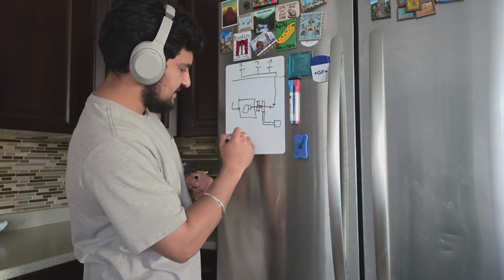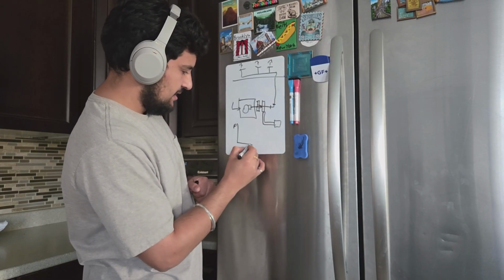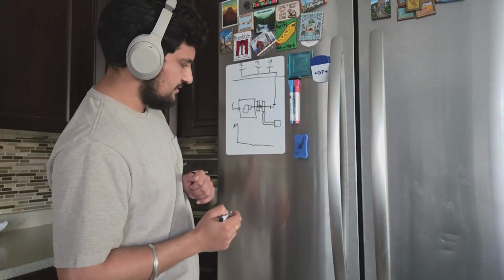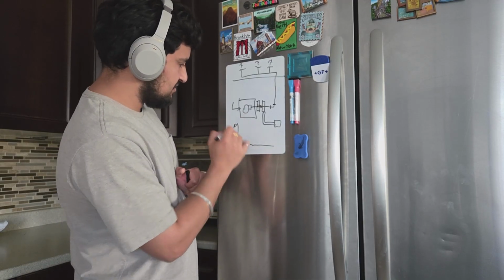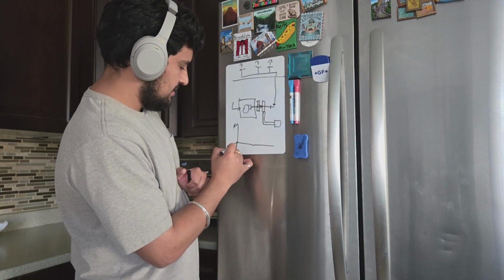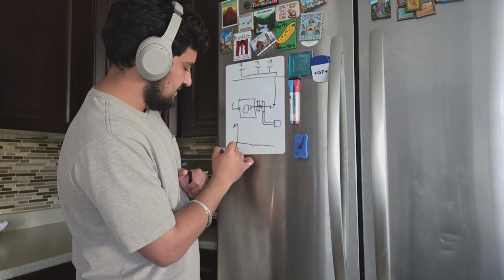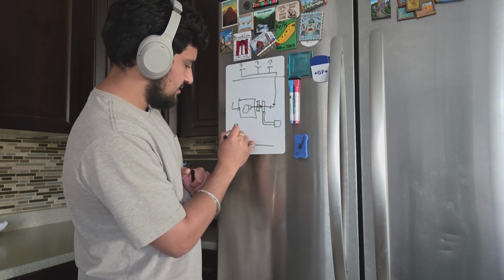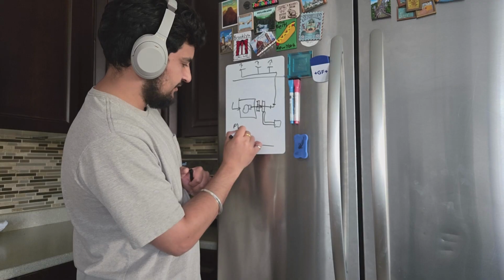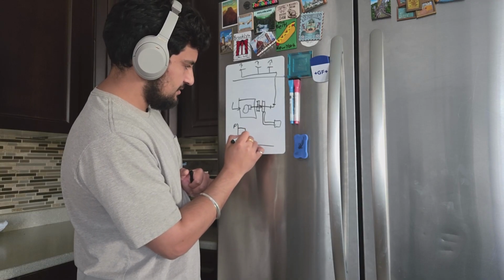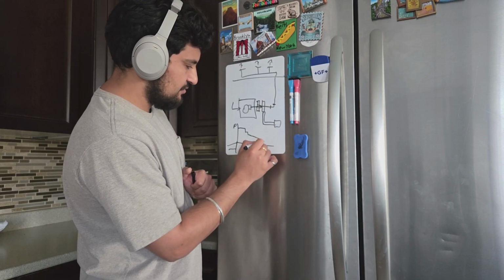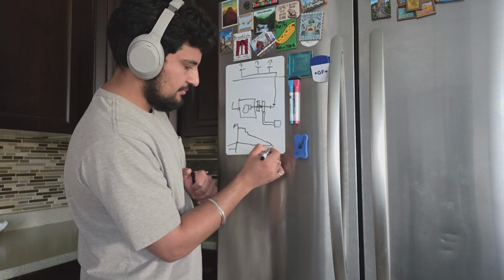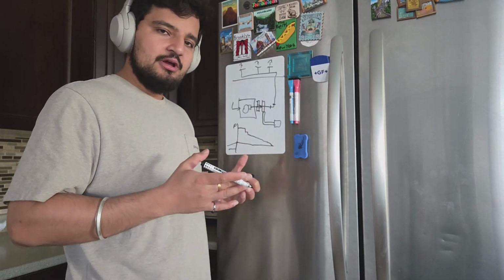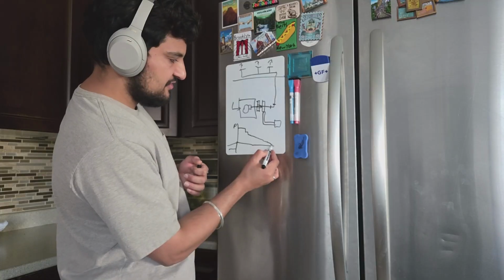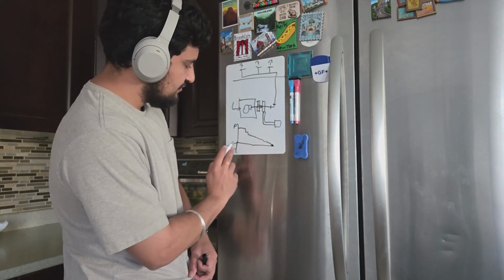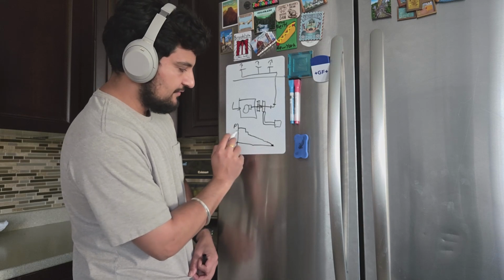So what ends up happening is it looks something like this, right? So you have your pressure and the distance. So as the air is traveling through the ductwork, the air is going to start off at some negative pressure on the back of the fan, and it comes up, let's say, as it goes to the fan, gets up to somewhere here, the fan boosts the pressure. As it goes to the filter, it drops down, then the cooling coil, it drops down, and then it's going to steadily decrease as it goes through the ductwork. And as it hits, for example, your room, which is probably at atmospheric pressure, which is zero pressure relative to the environment, the pressure is going to drop down to zero, right?